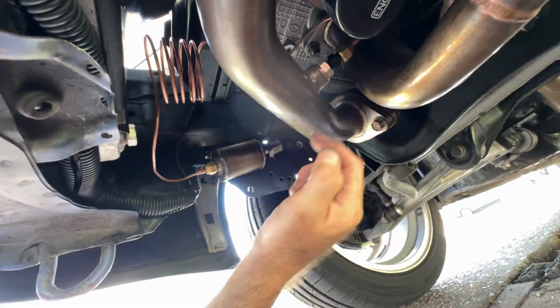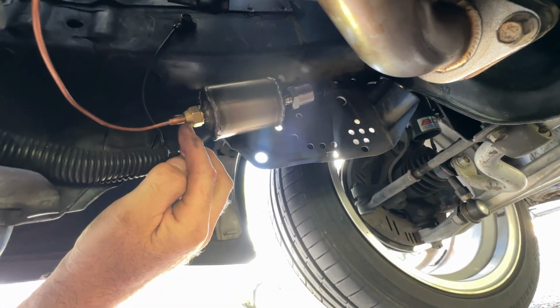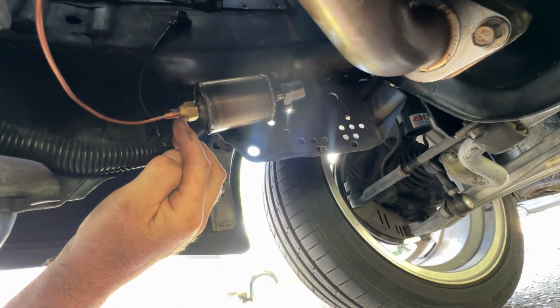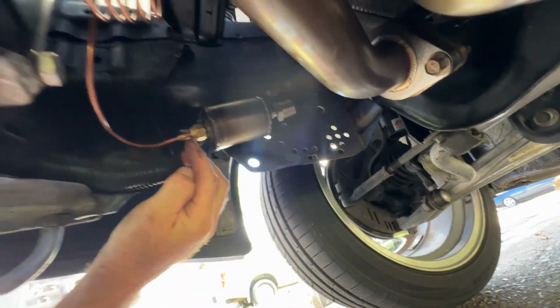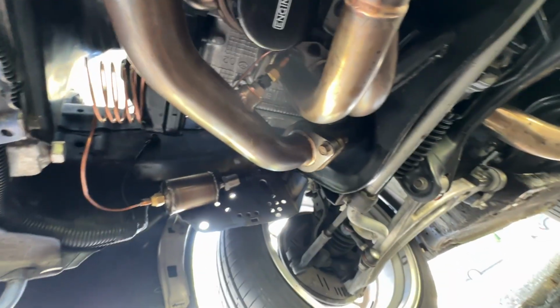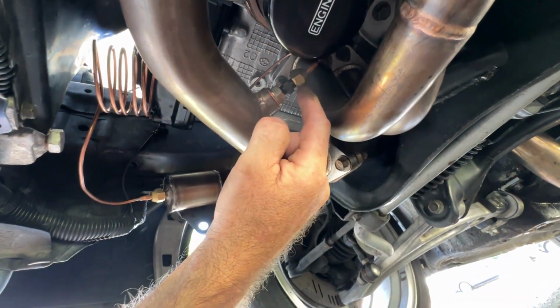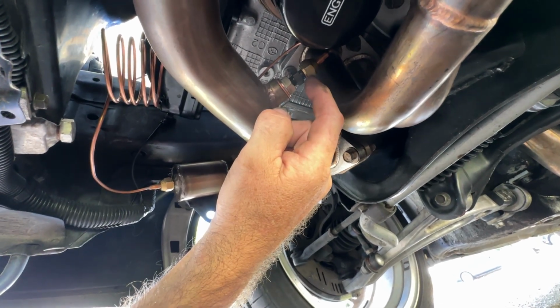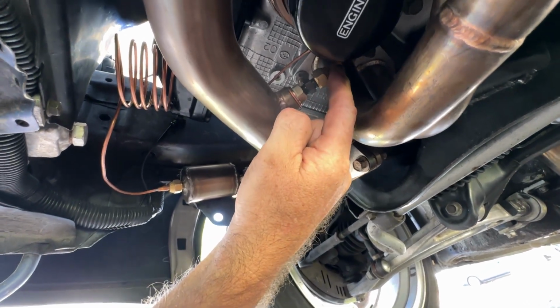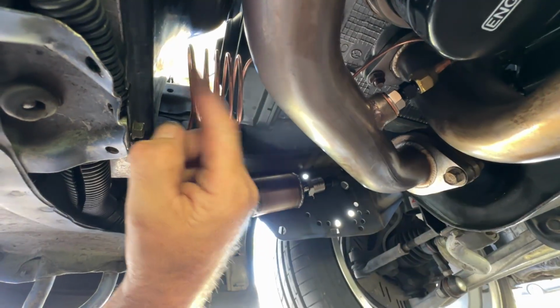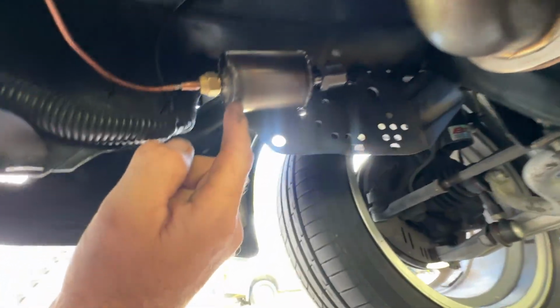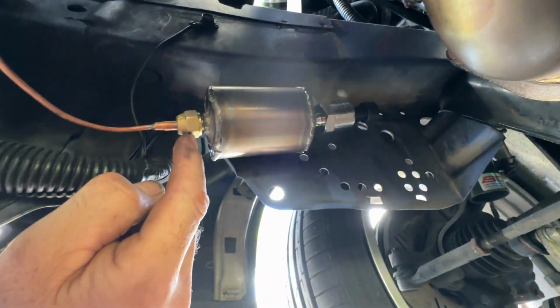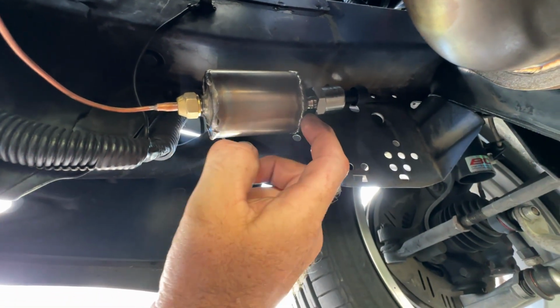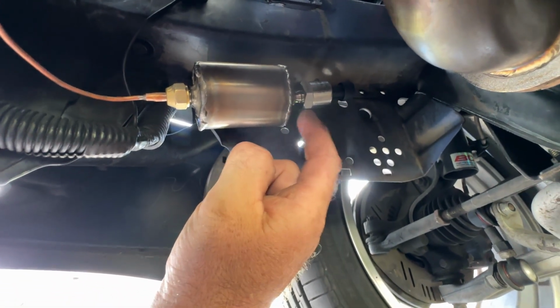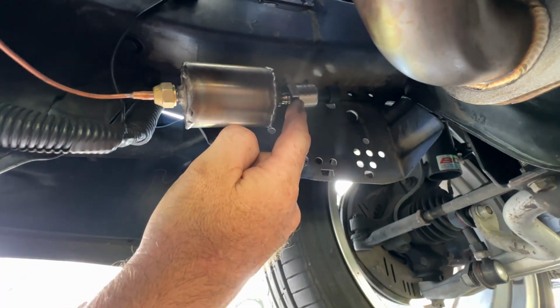These are AN4, a 37-degree flare. The copper pipe comes here, goes over here, through the loop, goes this way, and then comes to our canister. On each end of the canister, there's a female 1/8 inch NPT thread where my sensor is threaded in. I'll show you.